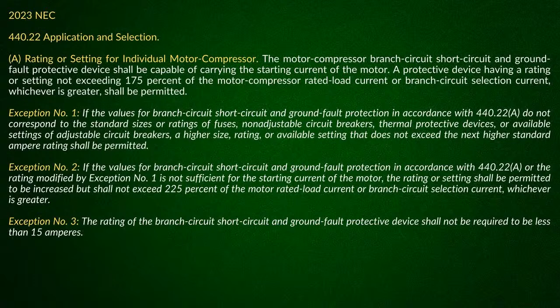Now, when you look at this, it talks about sizing the overcurrent protection device, and it tells you it has to be capable of carrying the starting current of the motor, and then it tells you that protective device will have a rating or setting not exceeding, now pay attention, not exceeding 175%. If you can't exceed it, that means you're going to drop down to the next standard size. That's your starting point. That's what we call the minimum. And then if you look at exception 1, you don't even have to do a calculation. If the motor fails to start due to inrush currents, then just go to exception 1. It allows you to go up to the next standard size. Exception 2 states if it still won't start, it allows you to have a rating or setting to be increased, but once again it shall not exceed 225%. That's your maximum. Once you calculate it, you can't exceed it, so you're going to drop down to your next standard size.